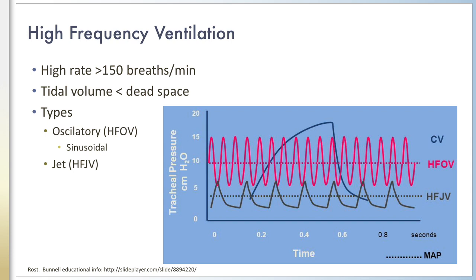There are two main devices on the market to deliver high-frequency ventilation. The oscillator, or high-frequency oscillating ventilator, which uses a sinusoidal pressure wave as shown in the diagram in pink, and the jet ventilator, or high-frequency jet ventilation, which delivers a pressure wave shaped like spikes, as shown in gray in the diagram.